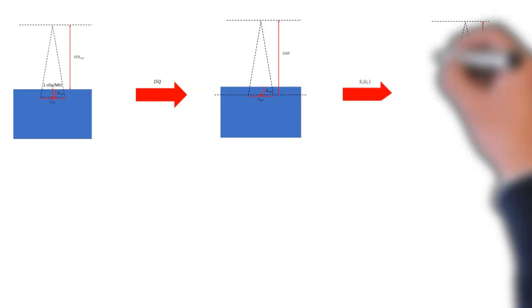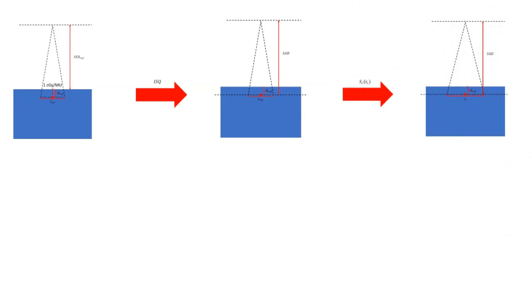And then after that, we can adjust our field size with the collimator scatter factor. So with that factor, we're accounting for the differential amount of scatter that is emanating from the collimators and the flattening filter.